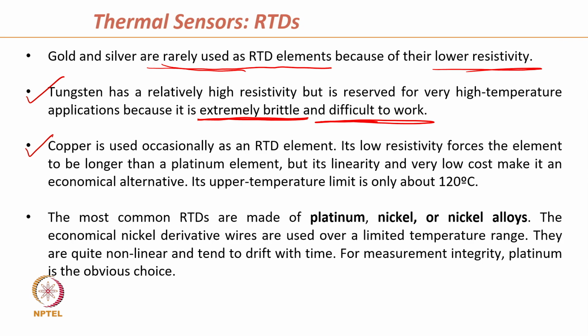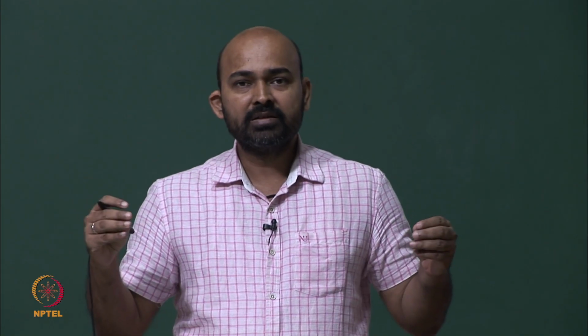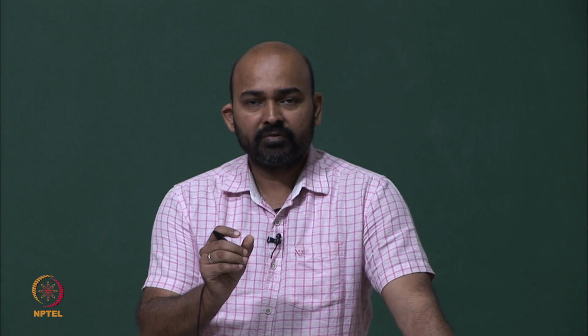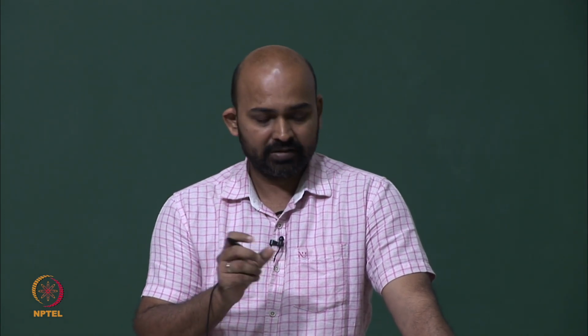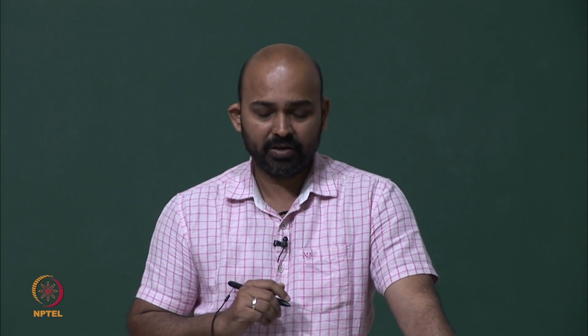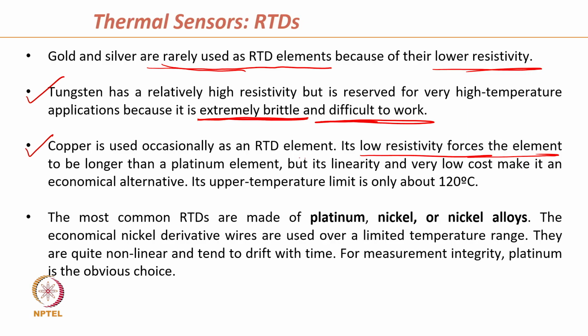Copper is also used occasionally as an RTD element. Its low resistivity forces the elements to be longer, because if the resistivity is lower, we need to have a longer wire to have certain resistance in ohm or kilo ohm range. Otherwise, for a small size sensor, the resistance of the copper will be in milli ohm, which will be very difficult to measure. But its linearity and very low cost make it an economical alternative. Copper is still used because of the good linearity and very low cost. Its upper temperature limit is only 120 degrees C. After that, the copper metal does not respond very well to the temperature gradients.